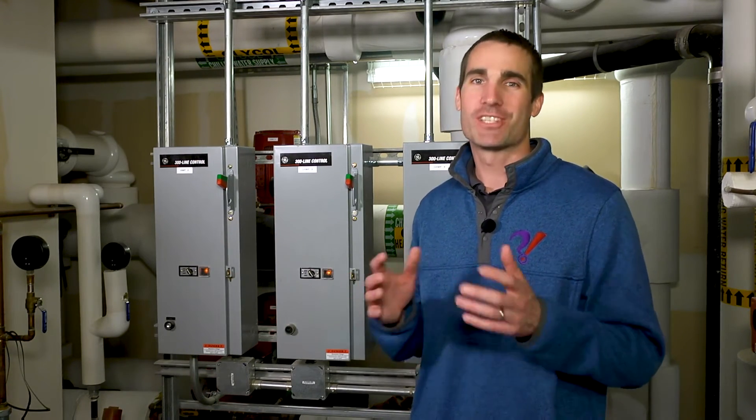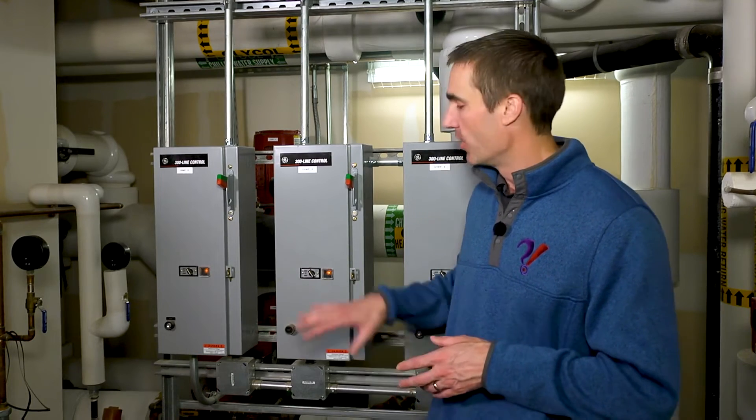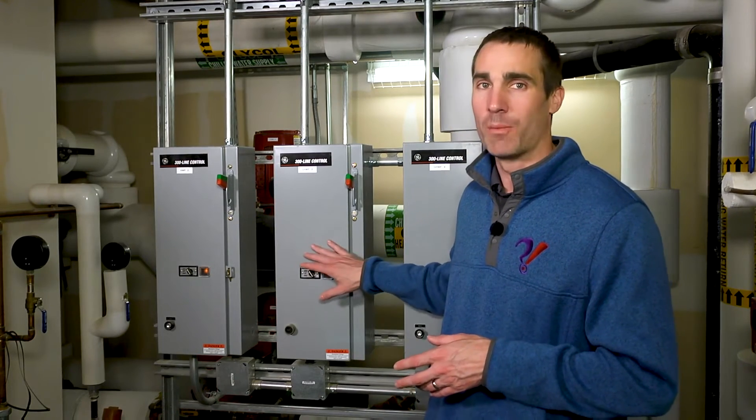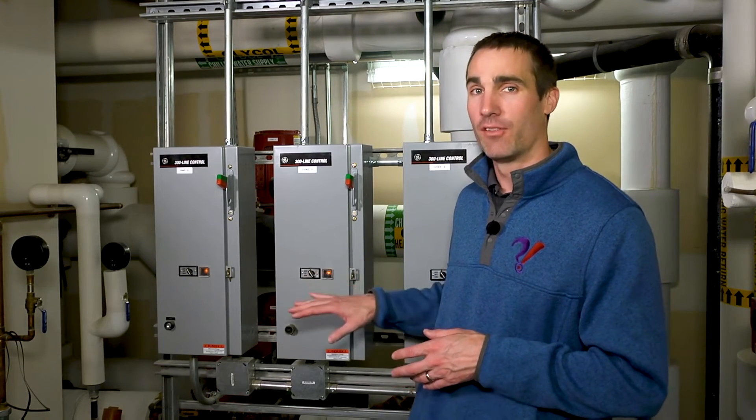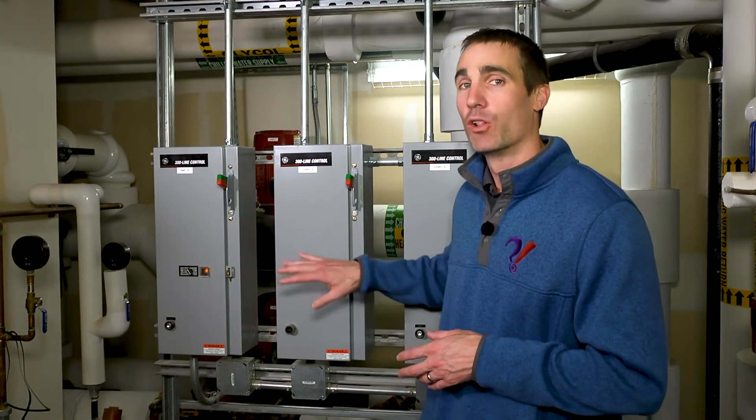So just because you have a building automation system dictating the operation of all your mechanical systems in your building, don't just stay at the computer. Go out in the field, look at these pieces of equipment, and make sure that they're not locally overridden one way or the other.